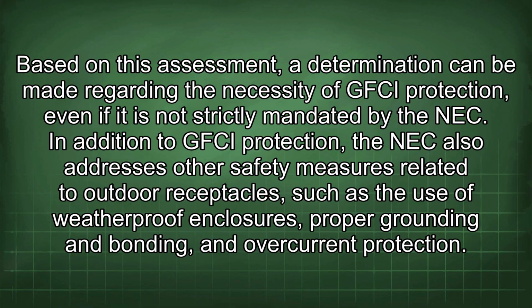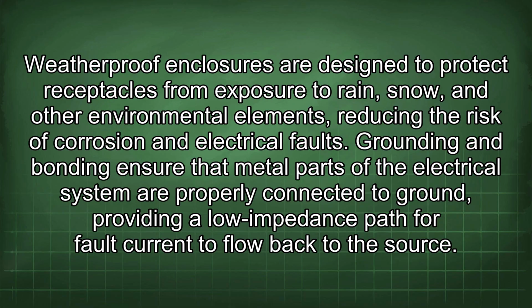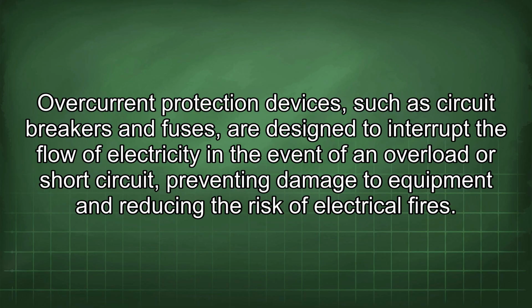In addition to GFCI protection, the NEC also addresses other safety measures related to outdoor receptacles, such as the use of weatherproof enclosures, proper grounding and bonding, and overcurrent protection. Weatherproof enclosures are designed to protect receptacles from exposure to rain, snow, and other environmental elements, reducing the risk of corrosion and electrical faults. Grounding and bonding ensure that metal parts of the electrical system are properly connected to ground, providing a low impedance path for fault current to flow back to the source. Overcurrent protection devices, such as circuit breakers and fuses, are designed to interrupt the flow of electricity in the event of an overload or short circuit, preventing damage to equipment and reducing the risk of electrical fires.